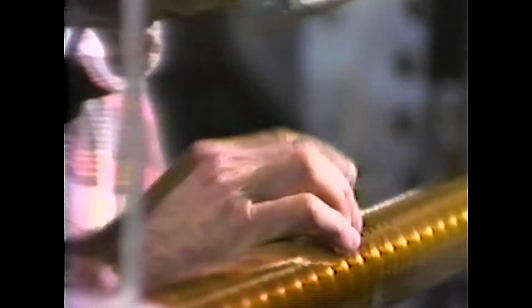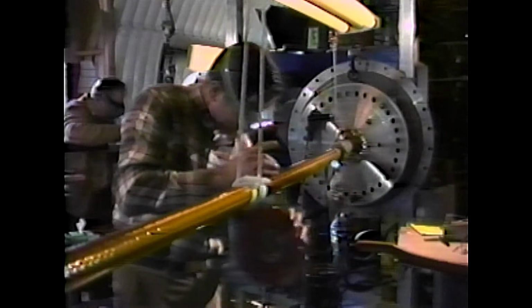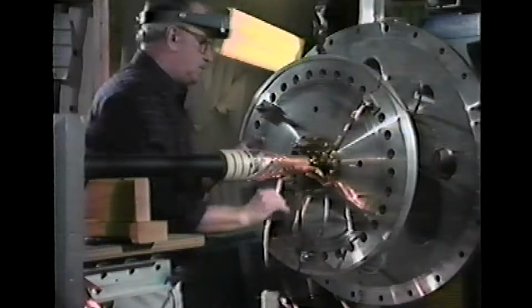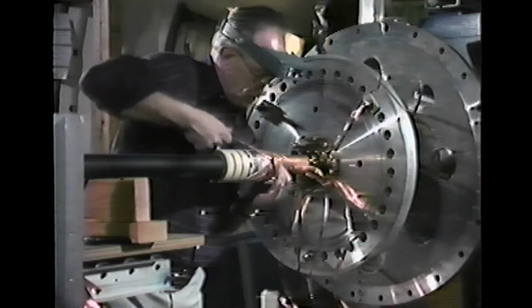The ends of the superconducting cables had to be prepared to match the joint to the electrical components of the termination. The electrical insulation is carefully made into a predetermined shape by the hand application of additional insulating tapes. Metal strips which carry the current when the cable is cold are also carefully shaped and trimmed to the correct length.